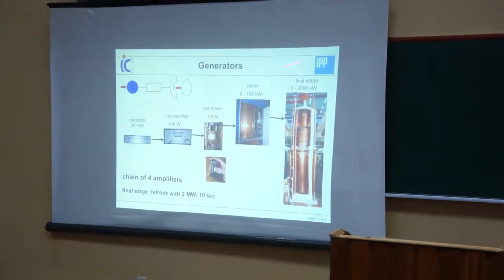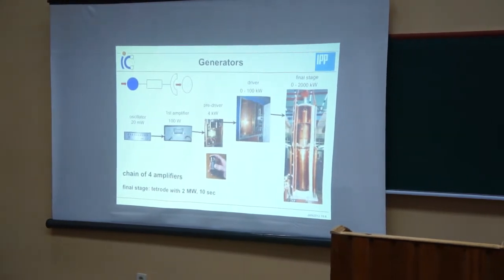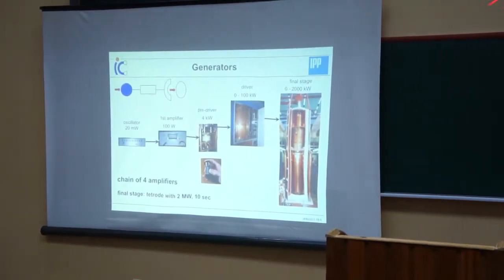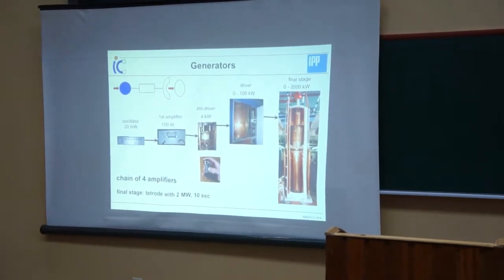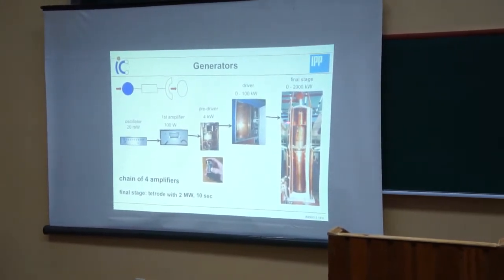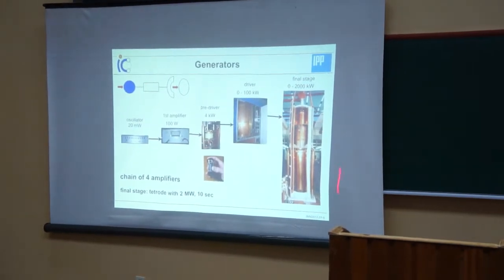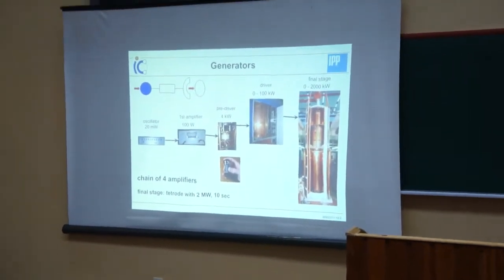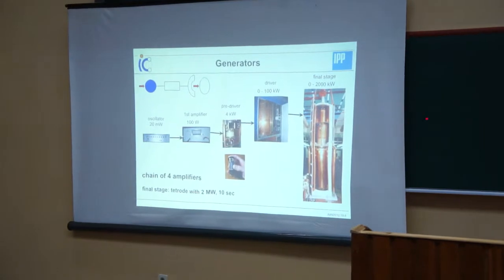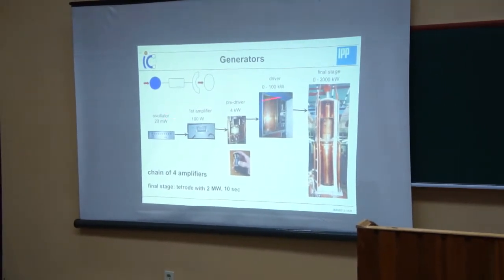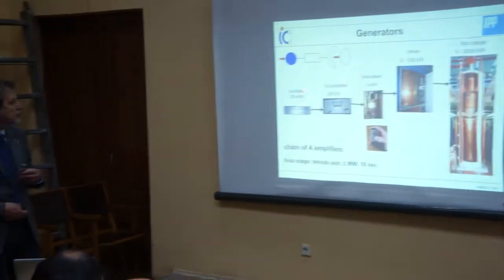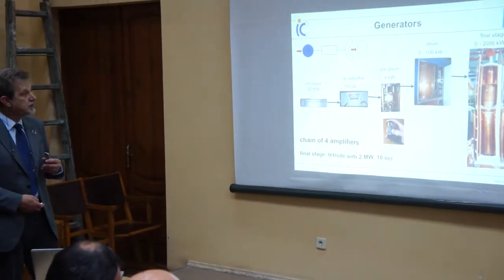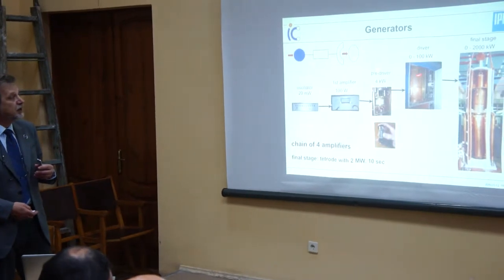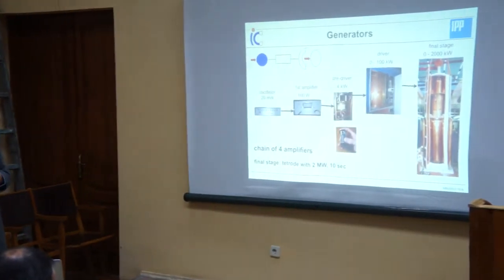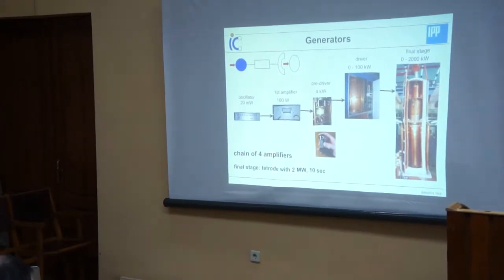Now, going back to the generators, I have said generator, but actually there are a number of generators. This is the final stage. The final stage is about 2 megawatt, and it has a height of something from here, the bottom, to the top of the picture there. So this is the size of this generator. This is the final stage of a series of amplifiers which actually start with 20 milliwatt. 20 milliwatt is first amplified to 100 watt, then to 4 kilowatt, and then to 100 kilowatt, and the last stage brings it up to 2 megawatt. So we have a chain of 4 amplifiers.